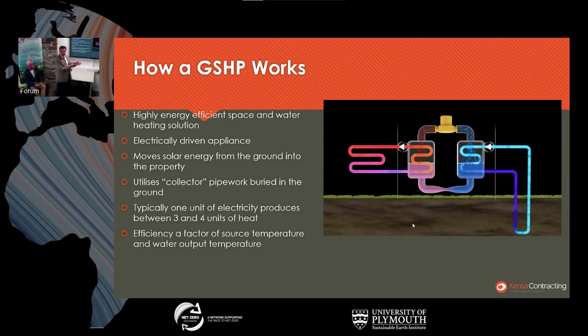So for the hour or so it's on at night time to create your hot water, your heat pump heats the water up to around 63 degrees. My Evo is stored at 60 degrees. For space heating, if it's a new house, it's around 45 degrees flow. For my house, which is an old Victorian, it's a bit higher at 50 degrees flow, so it can cope with my radiators.